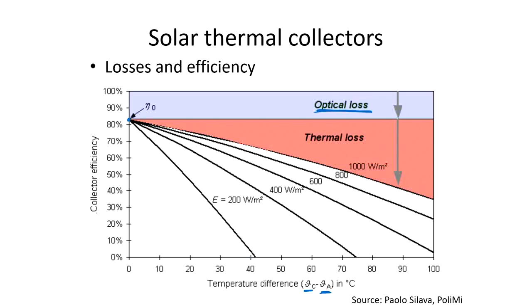As the temperature of the fluid in the collector increases, so do the thermal losses, and the efficiency curve decreases more steeply with increasing temperature difference. The collector has almost the same absolute thermal loss regardless of solar irradiation - once the mean fluid temperature is 30°C above ambient, there is a certain heat loss value. But as solar irradiation increases, the amount of usable heat also increases with the same loss value, so the collector efficiency increases as well.